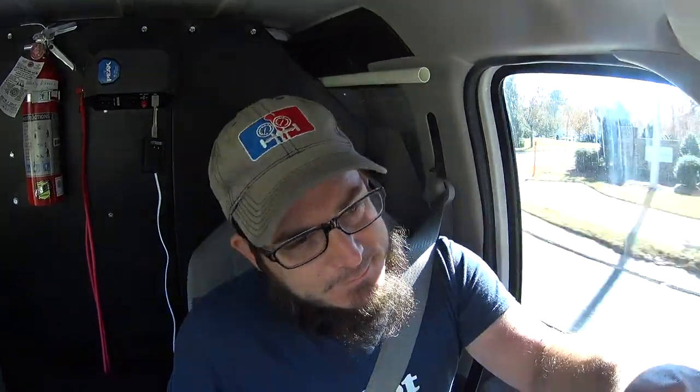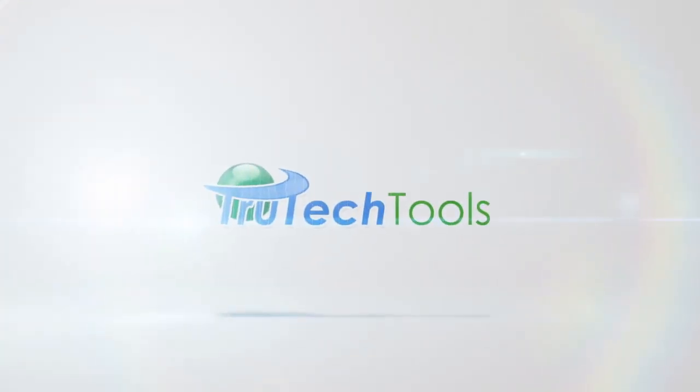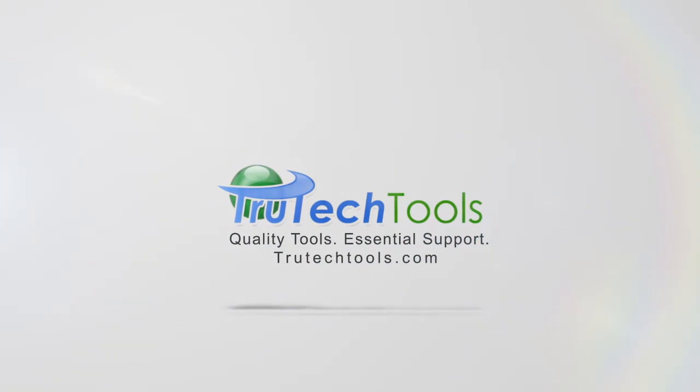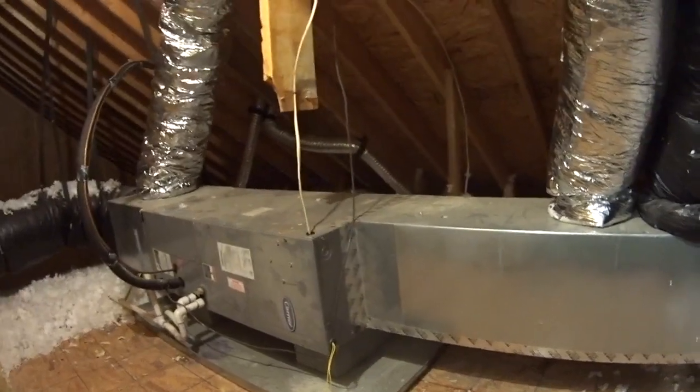We're going to hope that the wiring is sufficient up to the disconnect. Hopefully we're not wasting our time driving out there and not able to get a heat strip in the unit. Stay tuned. HVAC with Stephen Raritan is sponsored by TruTech Tools — quality tools, essential support — truetechtools.com. Well crap, we've got 14 gauge wire feeding the power to this air handler.